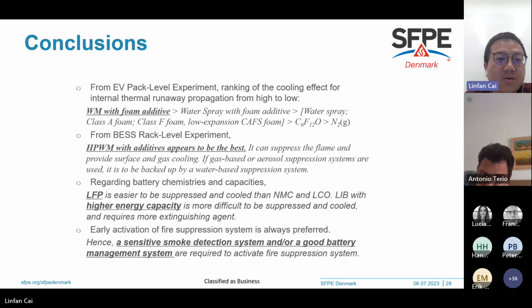So to conclude for the large scale experiments, the EV pack level and the battery energy storage rack level: for the EV pack level, I rank the cooling effect for internal thermal runaway propagation from high to low. Water mist with additive has a better cooling effect than water spray with foam additive, where water spray Class A foam, Class F foam, and low expansion compressed air foaming systems have similar cooling effect. But all of these are better than Novec gases and nitrogen inert gases.